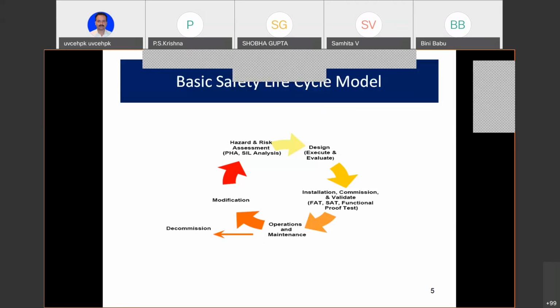Right. Coming back to reality: installation, commissioning, validating whether everything is right, and post-commissioning work also. What is FAT, as most of you may know? Factory acceptance test of the logic solver and the sensors, etc. What is SAT? Site acceptance test. After we do all that circuitry integration, we have to do that. Then this one, I'm reserving it for the last: functional proof test. We have done that because the sensors are working, valves are working, etc. But it has a very important aspect, which I'm going to give you before I finish this discussion.